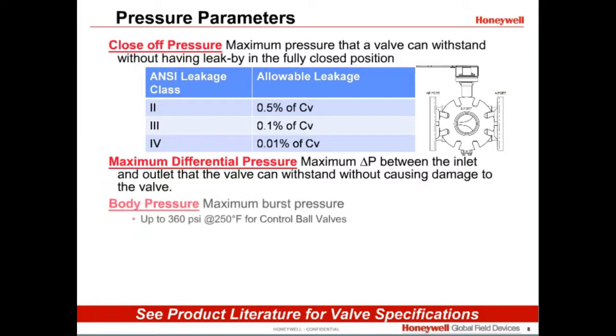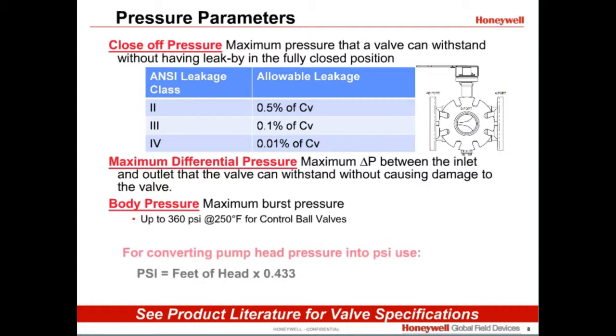The body or burst pressure is the pressure that the valve can withstand before developing external wall leakage. It is 240 psi for VBF and 360 psi for VBN valves. In the industry, psi and feet of head are both used to measure pressure. psi is equal to the feet of head times 0.433.